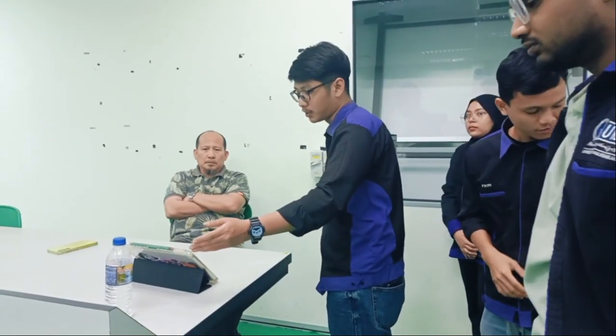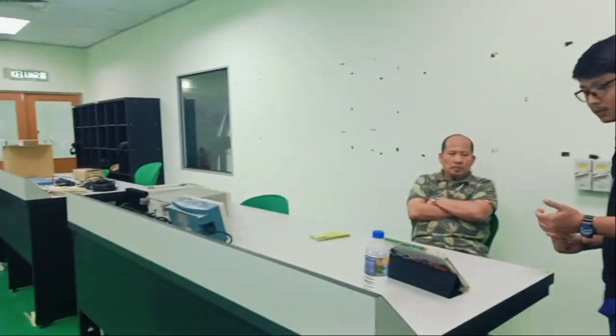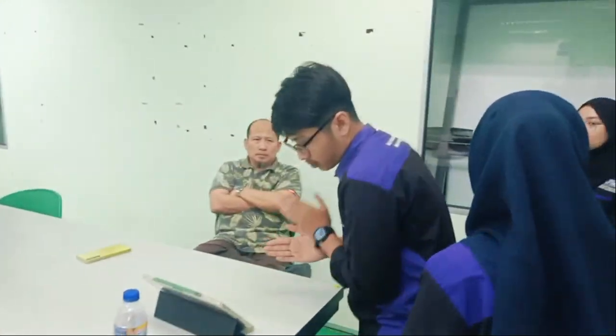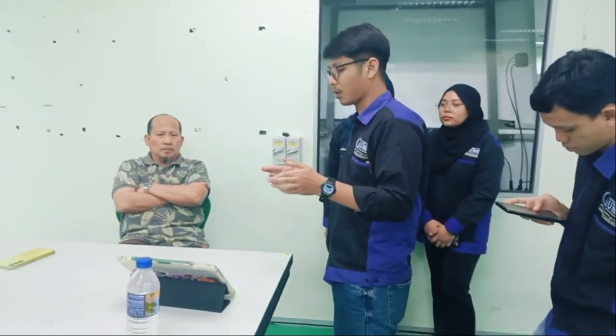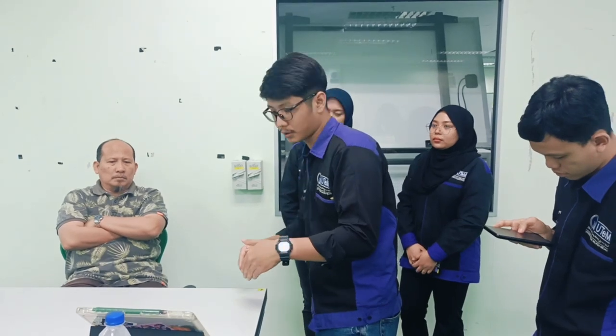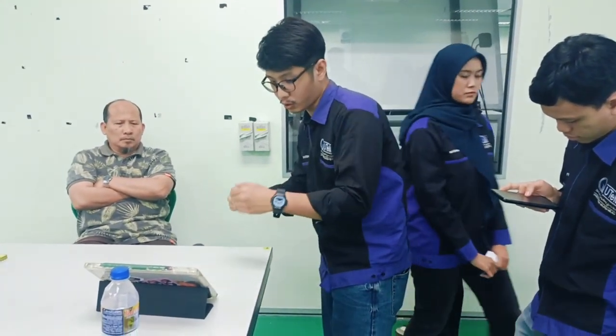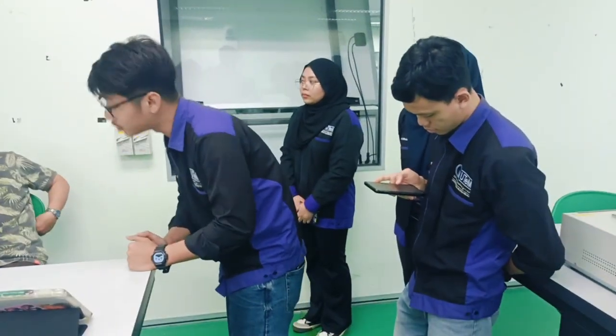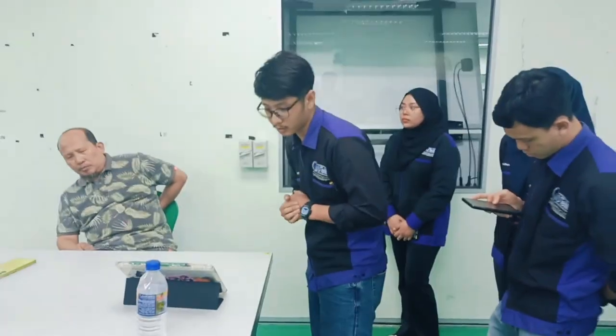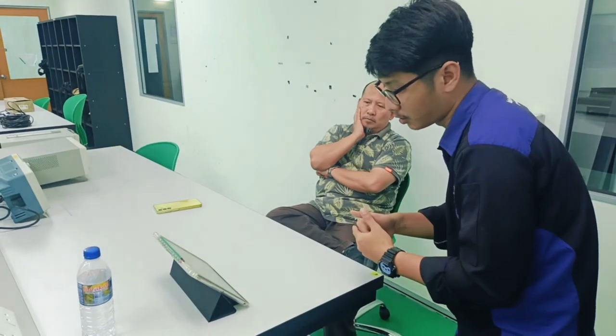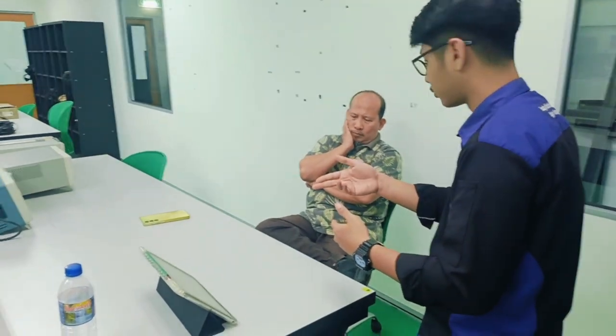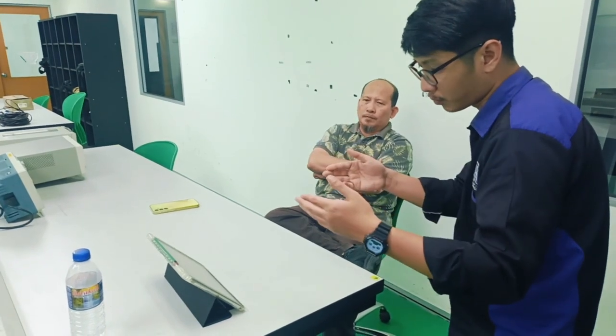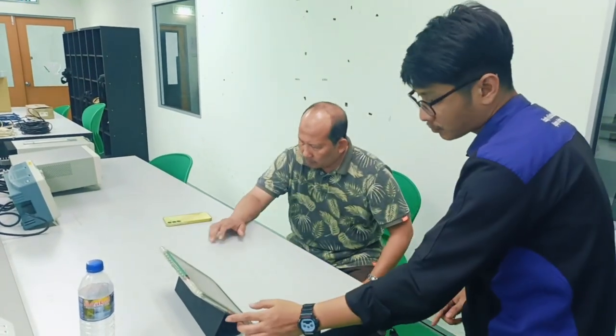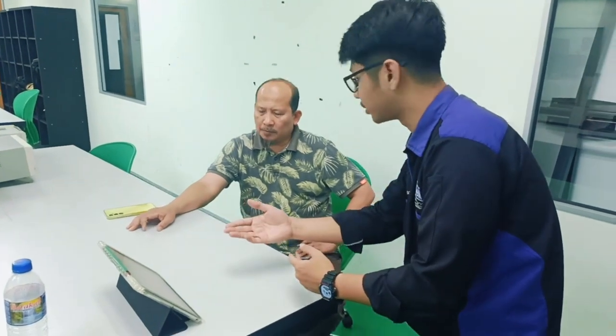Okay, for the method for measuring the system, a standard technique in electrical resistance testing is used, with the auxiliary electrode and pulse. So we inject a pulse through the auxiliary electrode, and then the earth electrode will be tested. That is the method for measuring.